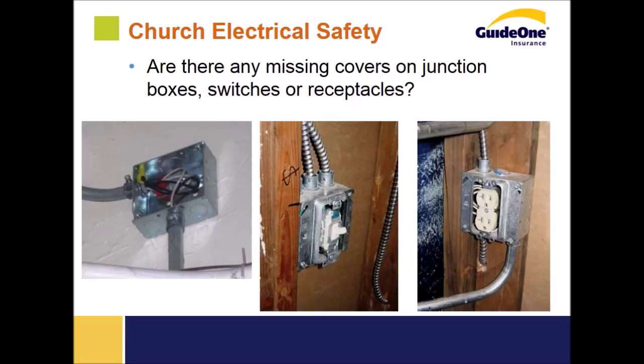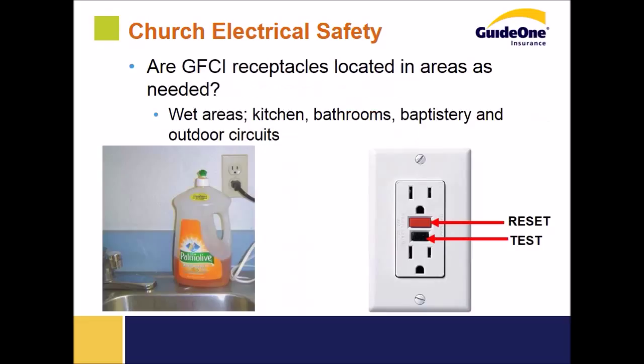Some other obvious hazards that we need you to report and make recommendations about are missing covers, whether it be on panels, junction boxes, switches, or receptacles. These need to be reported. It can lead to an electrocution hazard, physical damage can cause a short circuit or a fire, and rodents can enter. It's just a condition that needs to be reported and corrected.